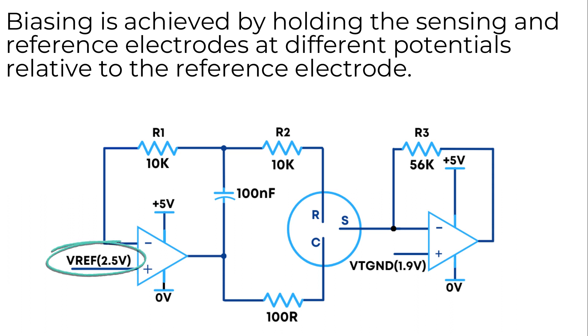And a 1.9 volt virtual ground voltage to the sensing electrode. Thus the sensing electrode is held at 600 millivolts below the reference electrode. The current produced by the sensor can be measured across the 100 ohm resistor as shown here.